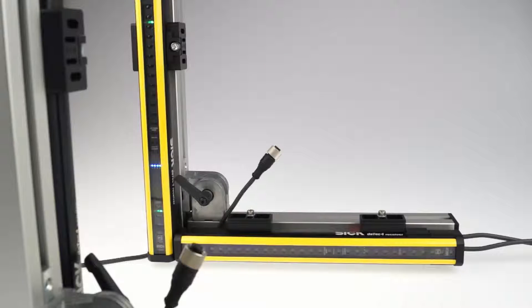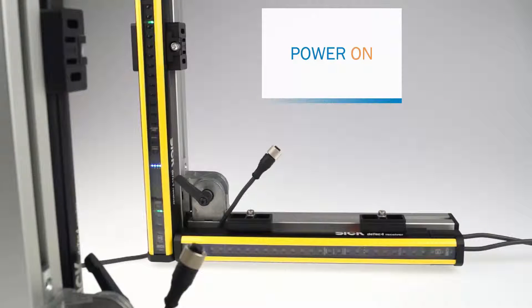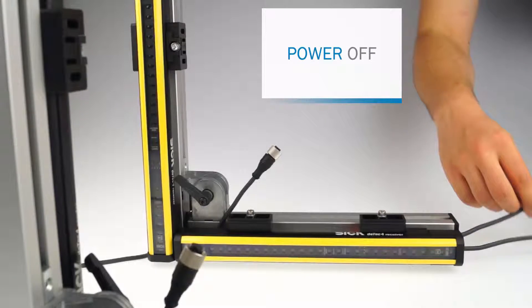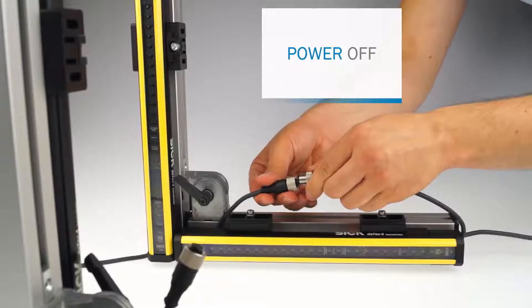To cascade another sender-receiver pair to an existing standalone system you need the system plug with extension connection on at least one sender and one receiver. Now after disconnecting the system from the power supply you simply connect the other devices to the extension connection from the system plug of the previous device in the cascade.